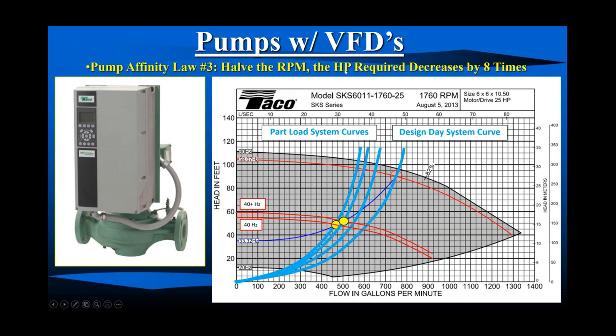Any decrease in RPM is a big deal horsepower savings wise. So any VFD on any pump is going to work better if we don't overpump. The only thing that makes us not overpump through any terminal is an automatic flow balancing valve. Any questions on that?